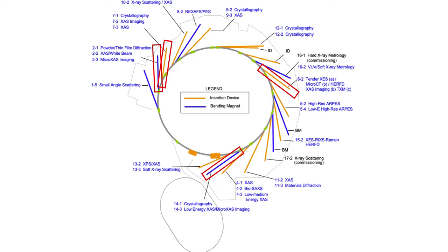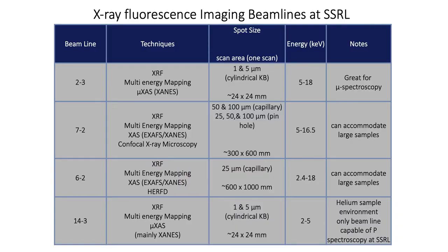SSRL has four micro-XRF beamlines: 2-3, 7-2, 6-2, and 14-3. These beamlines vary in their spot size or spatial resolution, field of view, and energy range. Beamline 2-3 has a spot size of 1 or 5 microns, a field of view of 24 by 24 millimeters, and an energy range of 5 to 18 keV. Beamline 7-2 has a comparable energy range but a coarser spatial resolution of 50 or 100 microns and a much wider field of view of 300 by 600 millimeters.